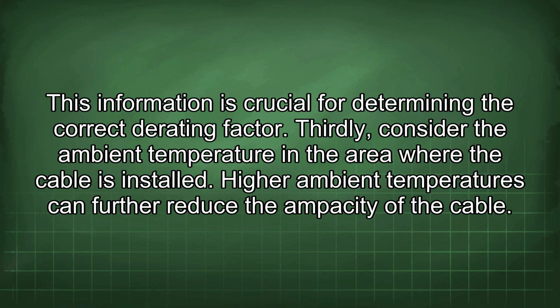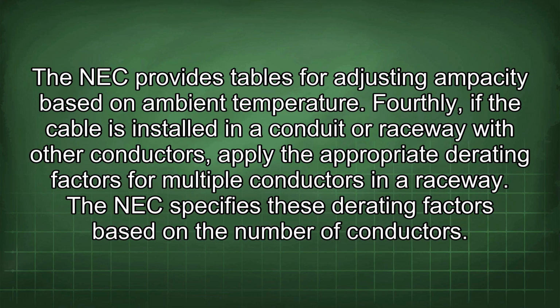Thirdly, consider the ambient temperature in the area where the cable is installed. Higher ambient temperatures can further reduce the ampacity of the cable. The NEC provides tables for adjusting ampacity based on ambient temperature. Fourthly, if the cable is installed in a conduit or raceway with other conductors, apply the appropriate derating factors for multiple conductors in a raceway. The NEC specifies these derating factors based on the number of conductors.